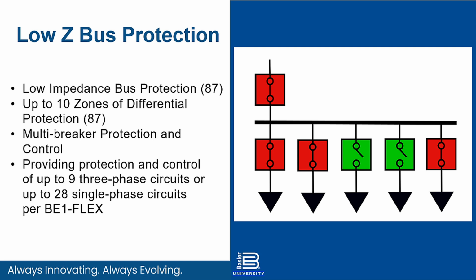So there are applications where high impedance bus protection is beneficial. Speed happens to be one of those specific points. But in many applications, the speed variance between low impedance and high impedance isn't significant enough to outweigh the benefit of going to low impedance. With the Flex, we can do up to 28 current inputs into a single box. And with that, we can theoretically do up to 28 single phase circuits protected by a single protective relay. We would do that with single phase and potentially even use multiple devices for a three-phase system.